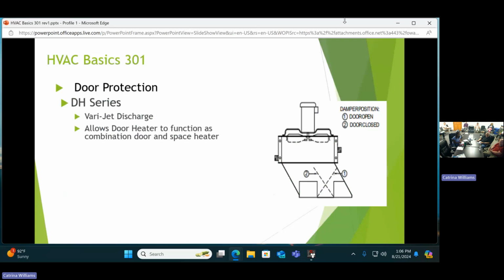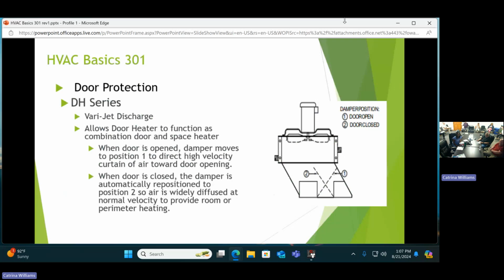So when the door is not open, you're not worried about that. You can use it for a space heater. And what that is, when the door is open through the door switch, it's going to drive a damper to position 1. That's going to drive the air through a narrower chute and have a high velocity at the door again, to stop as much of that cold air as it can. But when that door closes, that switch opens up, the damper goes back to position 2, a different position for a normal velocity, to provide either room or perimeter heating.